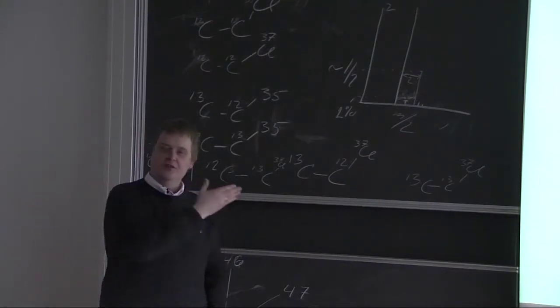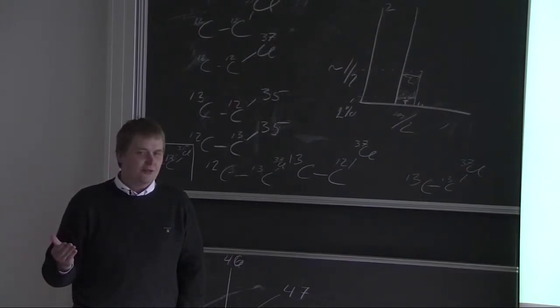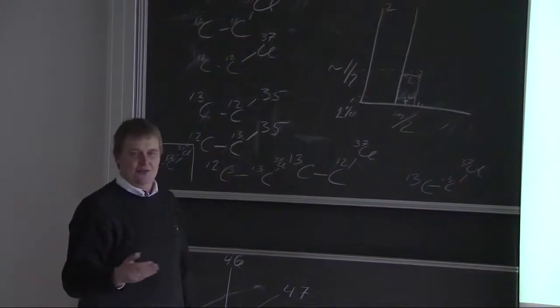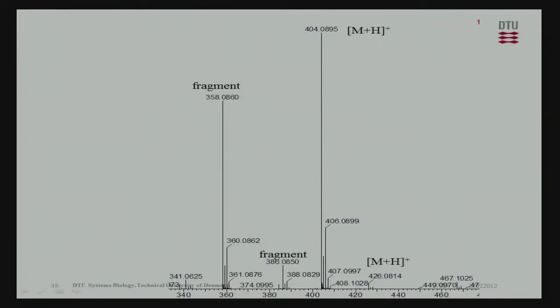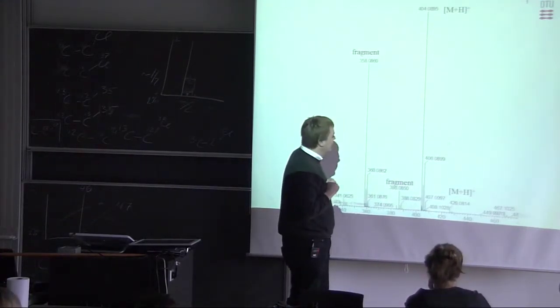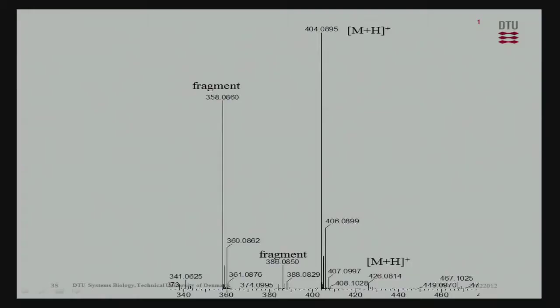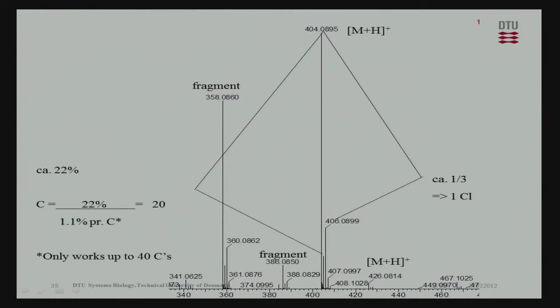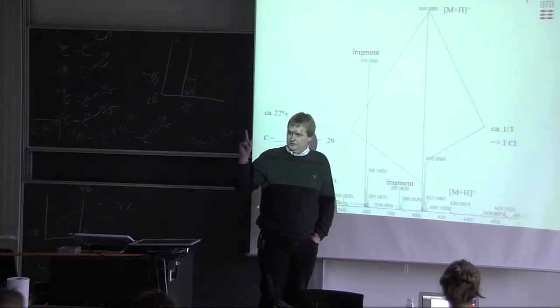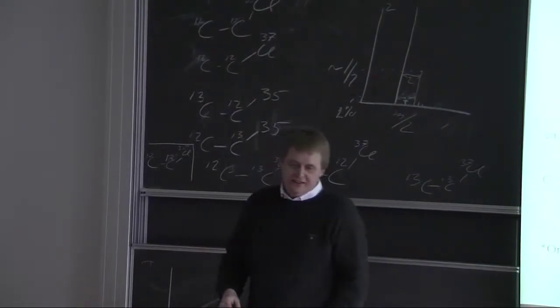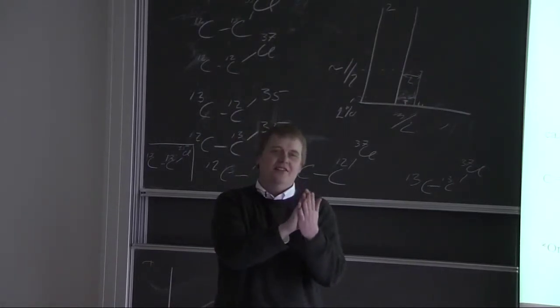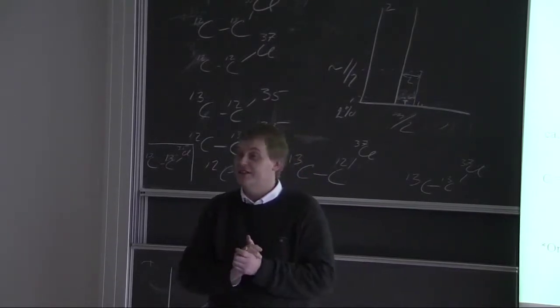Also, your mass spectrometer should always give you this isotope pattern. If you have a mass spectrometer and the isotope pattern is not fitting, your instrument is not working well. And it will not be able to quantitate or do anything. So, an example. We have our molecule. We'll come back to why this should actually be sodium. We have our protonated molecular ion. We can see a third here. So by this, about a third, we can say we have one chlorine in. We don't have two. If you have two in, it looks differently. Because then you can have more combinations up here and it's going to be a nightmare. Any mass spec book will usually have the printed isotope patterns of one, two, three, four chlorines, one bromine, one chlorine, one bromine, and so on, all the combinations.